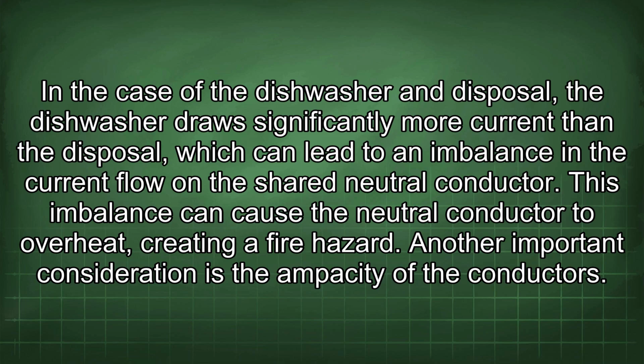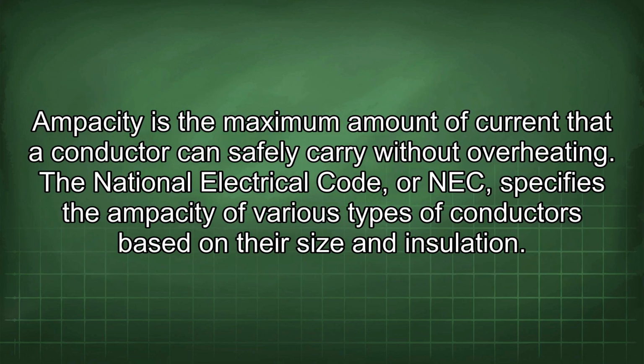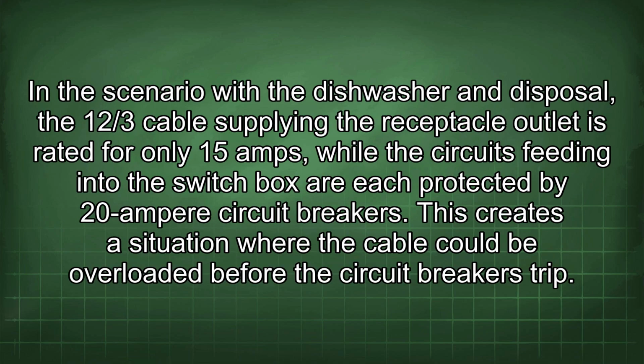Another important consideration is the ampacity of the conductors. Ampacity is the maximum amount of current that a conductor can safely carry without overheating. The National Electrical Code, or NEC, specifies the ampacity of various types of conductors based on their size and insulation. In the scenario with the dishwasher and disposal, the 12/3 cable supplying the receptacle outlet is rated for only 15 amps, while the circuits feeding into the switch box are each protected by 20 ampere circuit breakers. This creates a situation where the cable could be overloaded before the circuit breakers trip.